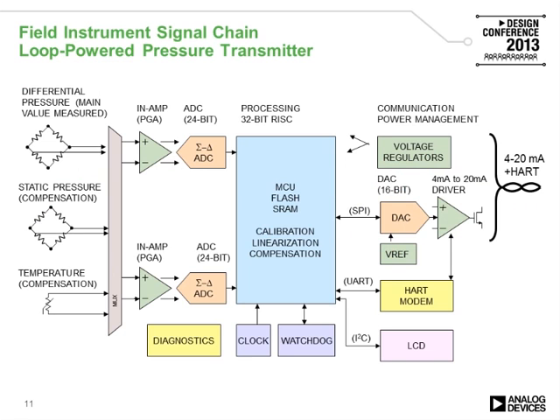To give a general diagram of a smart transmitter — in this case specifically a pressure transmitter — we have our sensor front end. This connects to some sort of analog signal conditioning to analog-to-digital converter. This digital data is then processed in our microcontroller, which performs calibration, linearization, compensation, as well as handling a number of other functions. And then lastly, this is transmitted back to our PLC/DCS, in this case by a 4 to 20 milliamp loop. There may also be a peripheral such as an LCD screen.